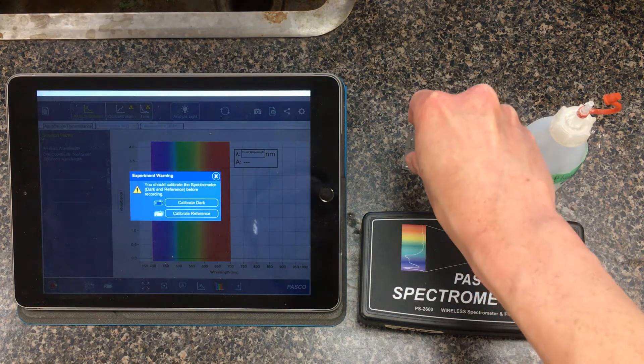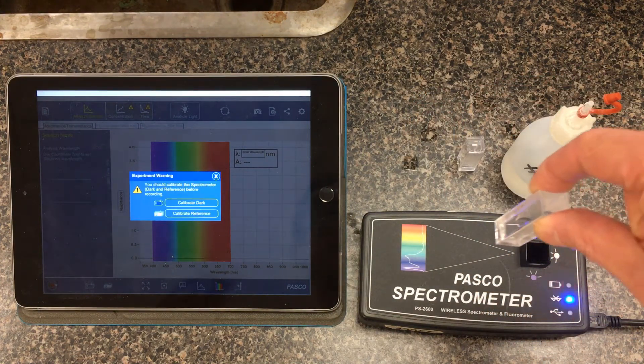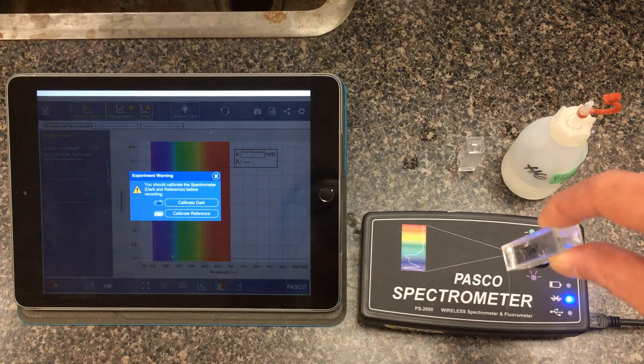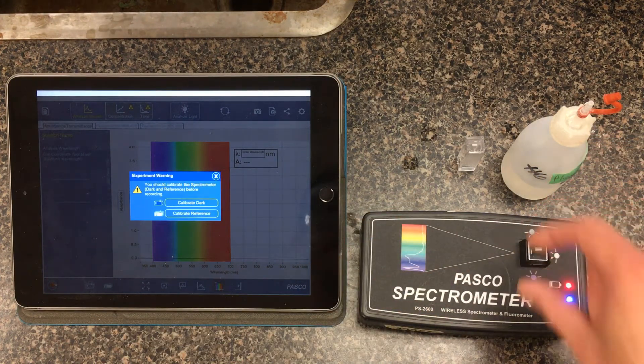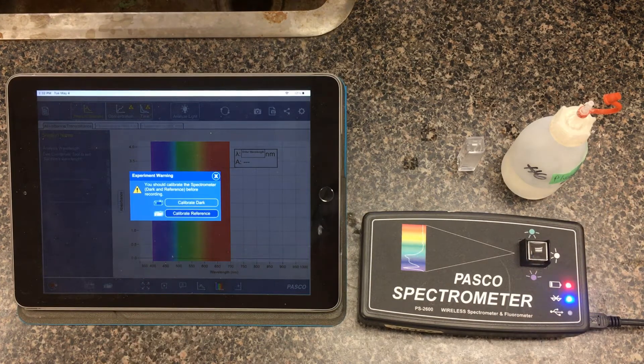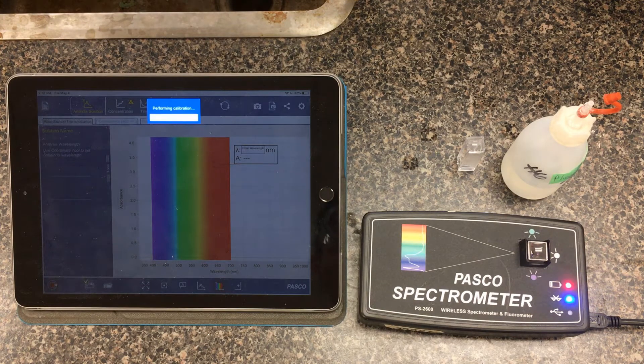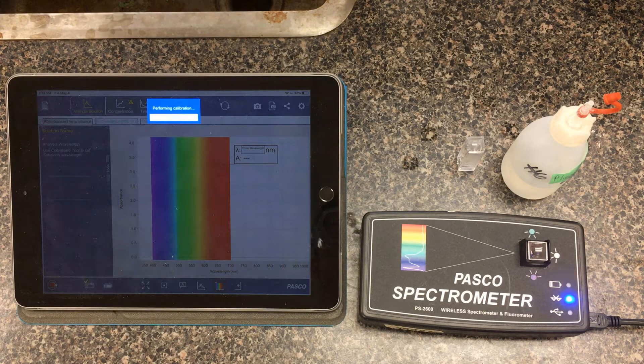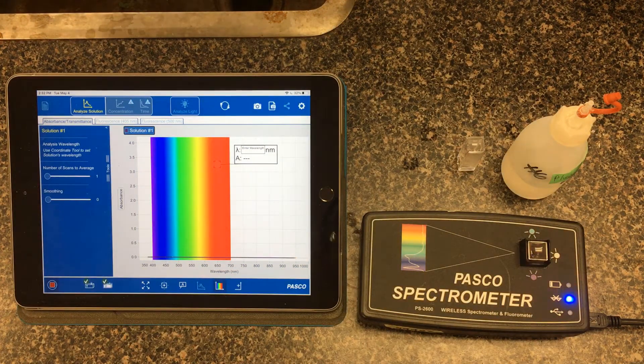I have my blank solution here. Just double-check your cuvette — sometimes cuvettes have two clear sides and two frosted sides, but this one is clear on all four sides, so we're fine. Light is going in side to side. I'm going to press the calibrate reference button. That's how the spectrometer knows what traveling through a centimeter of water looks like, and it will automatically subtract this blank from my actual solution.